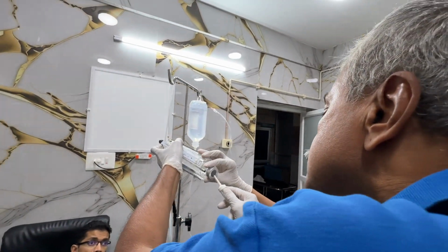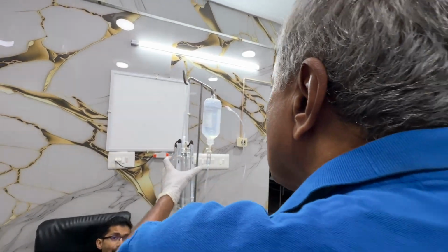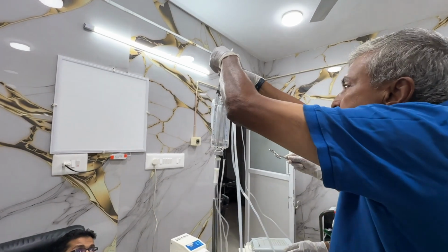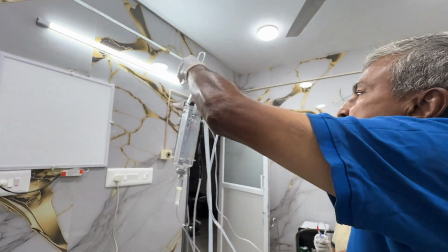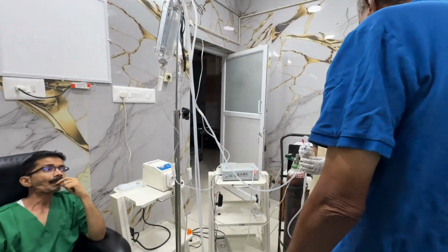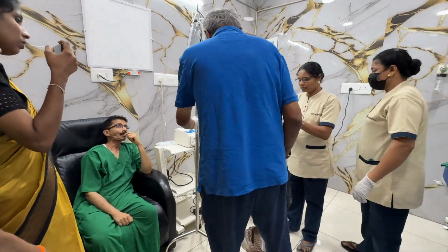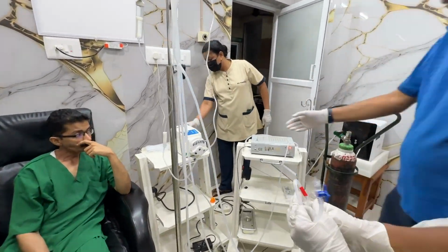The bottom silicone tube also has a big round circle through which the recipient tube is inserted. The height of the ultraviolet irradiation chamber is adjusted, and now the system is primed and ready for beginning to start the procedure.